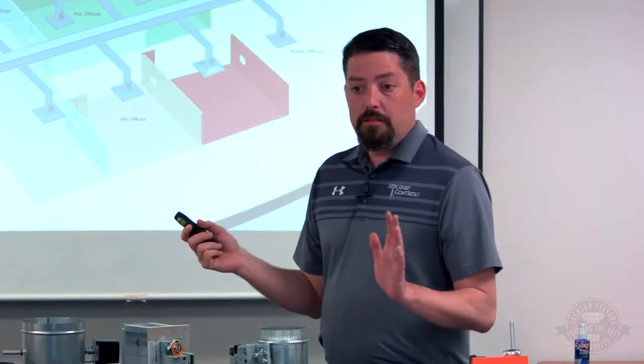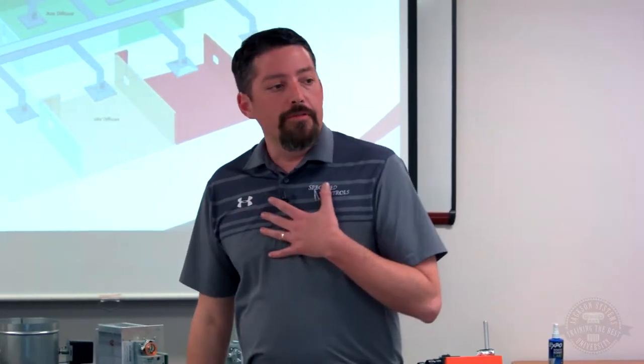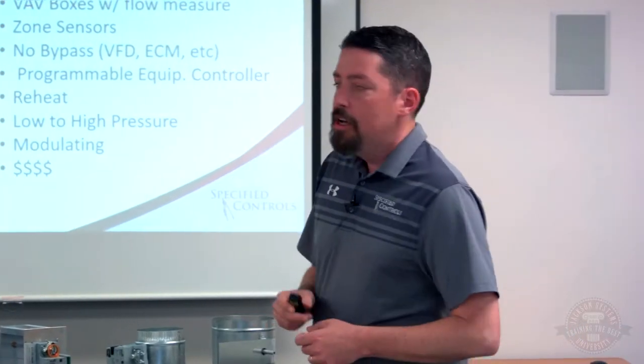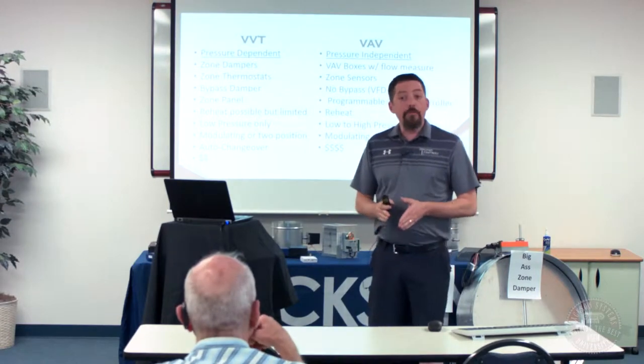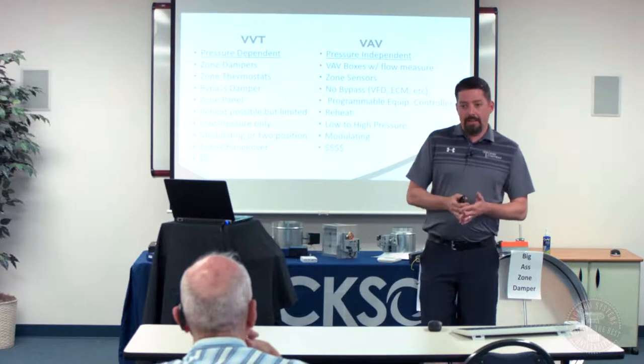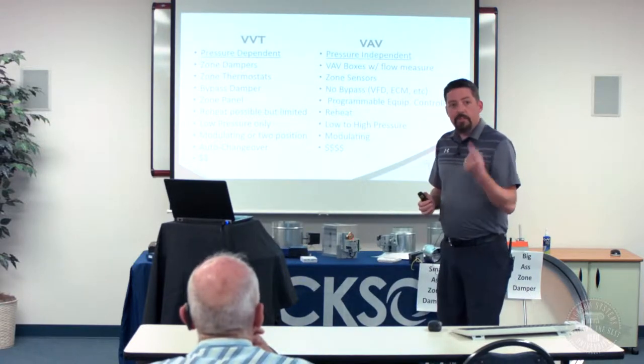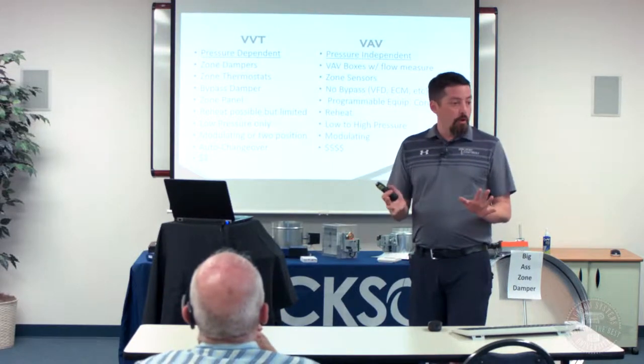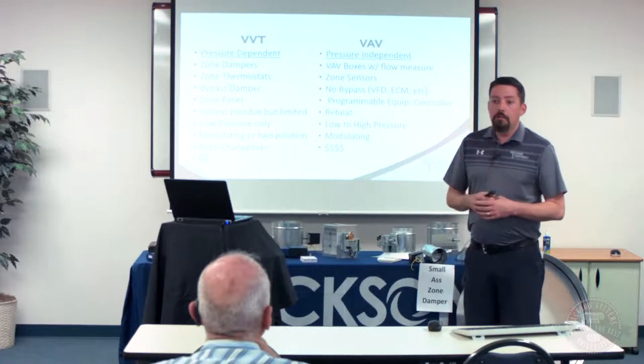What we want is zone dampers throughout the space instead of a VAV box — this is what we refer to as VVT zoning, meaning Variable Volume and Temperature. VVT zoning is pressure-dependent, has zone dampers not VAV boxes, uses zone thermostats not sensors, and has a bypass damper. You'll often hear a VVT system referred to as a bypass system. It has a zone panel, reheat possibilities limited to electric heat only, and is low pressure.